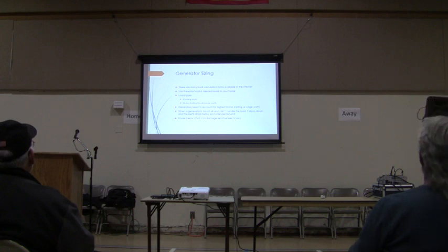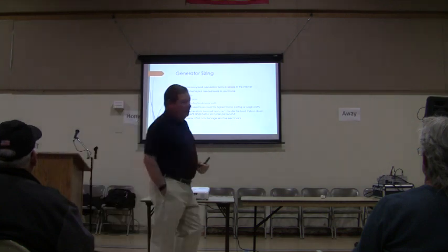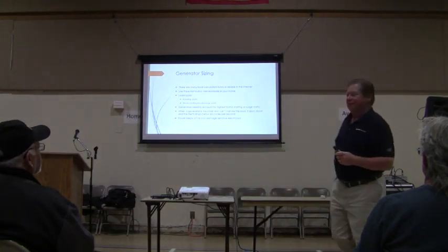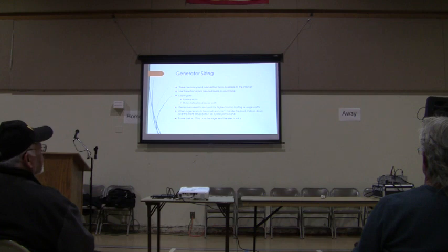When a generator is too small and can't handle the load, it slows down. When it slows down, it's no longer turning at 3,600 RPMs. It's generating less hertz. Below 57 hertz can damage sensitive electronics. So if you have too small of a generator, your TV may not work so well. So how do we know?